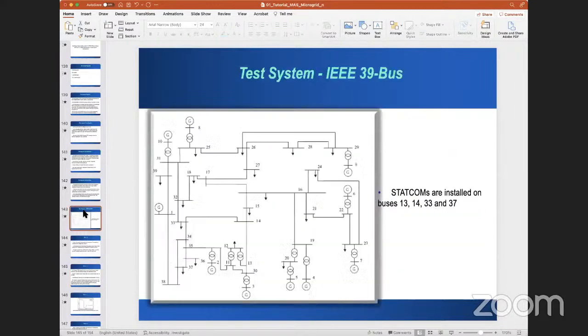Okay, now see what happened now. It makes sense also, right? Means the voltage that we violated on bus 15, there is no line, so the influence that 14 has is more influence on bus 15. So statcom at bus 14 has more influence on bus 15 voltage rather than statcom at 33, or statcom at 37, or statcom at 13. 13 also will have some influence, depending on how long the line is from 13 to 14.